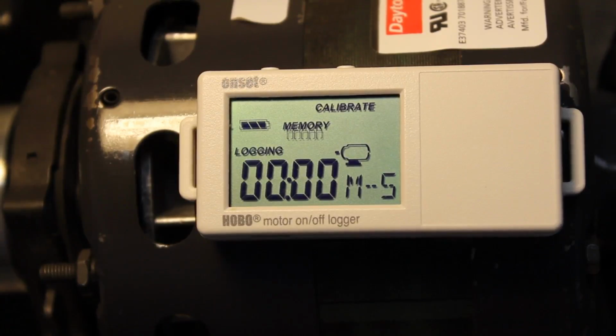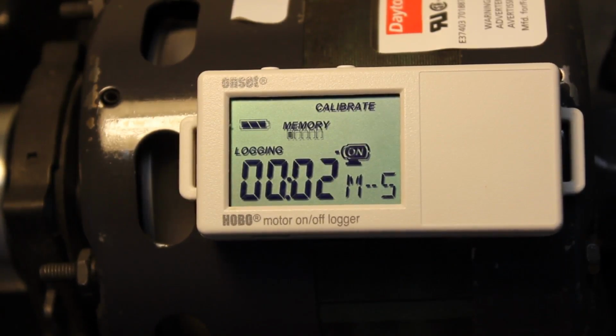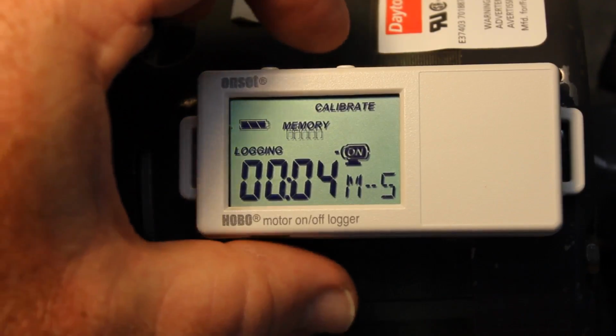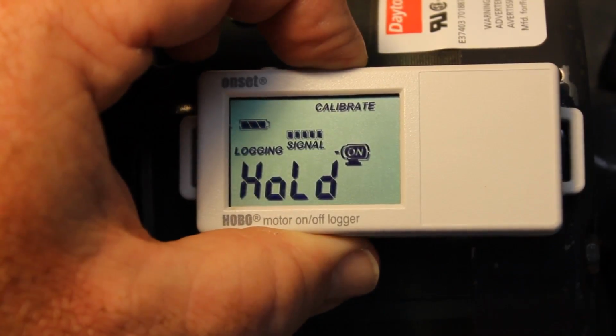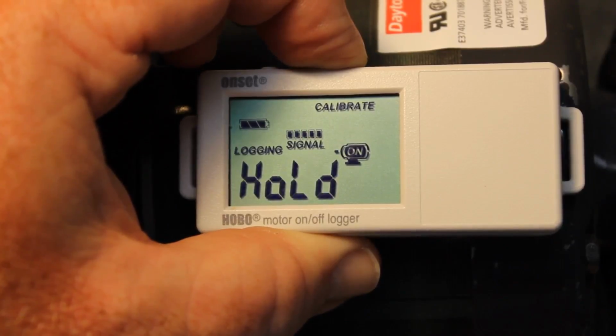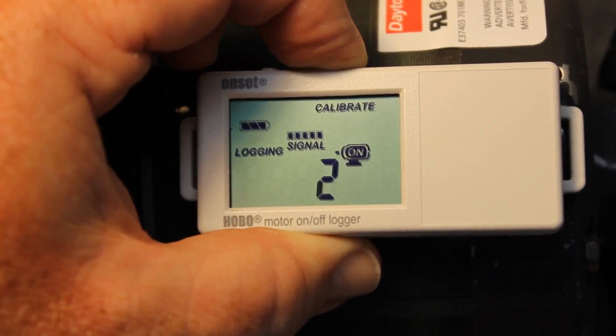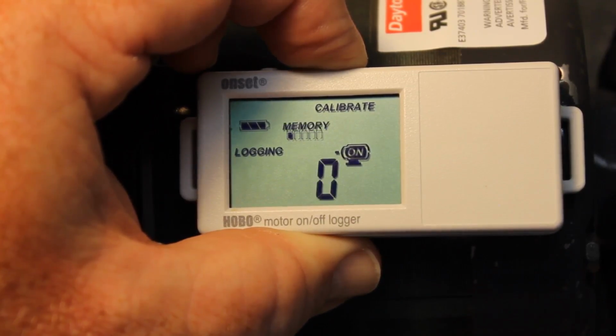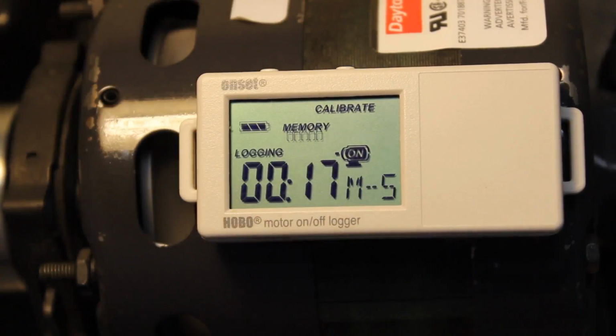We're going to turn it on, and the motor is now running, and you'll see the little on indication come on in the icon, and the timer will begin to increment. And what we're doing now is calibrating it. Press and hold the button. It counts down from 4, and then it will say auto cal pass. Now we can release it, and it's recording its runtime.